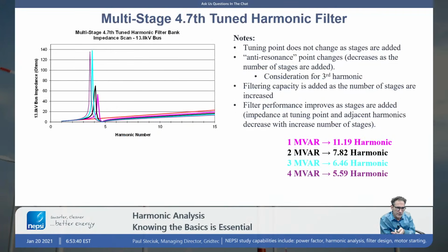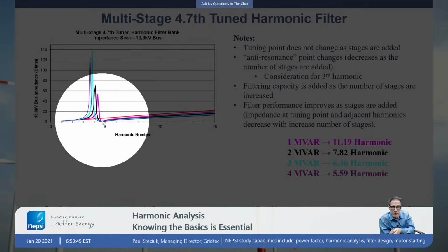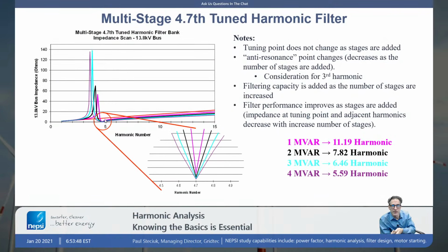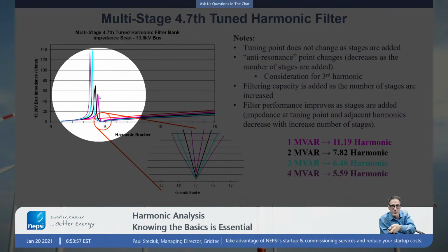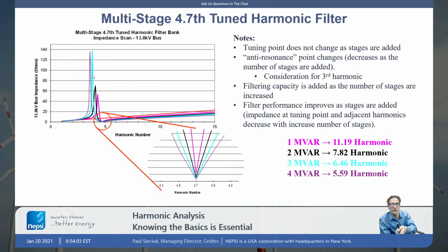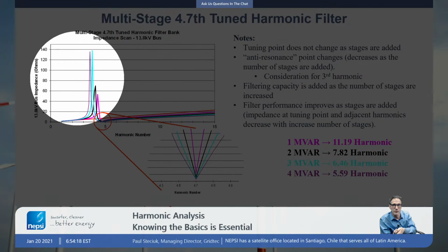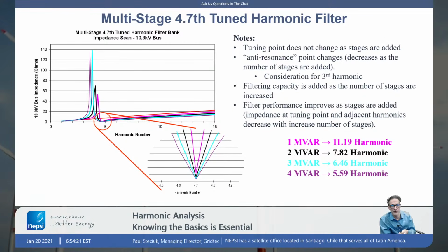For multi-stage banks, in this situation we have multiple impedance curves, but you can note that the impedance at the tuning point is always the same, and you can kind of zoom in on that. As we add more filters, we improve our filtering capability, but our resonant point is always beneath our tuning point. We do have a shifting resonant point beneath our filter, and that's something that's sometimes of concern on networks that might, say, have a fourth harmonic. A rectifier, for instance, with some unbalance in the network can put out some fourth harmonic, and that's something of concern. Sometimes we have third harmonics in the network, and this impedance curve could potentially shift back to the third, so something to be concerned about.